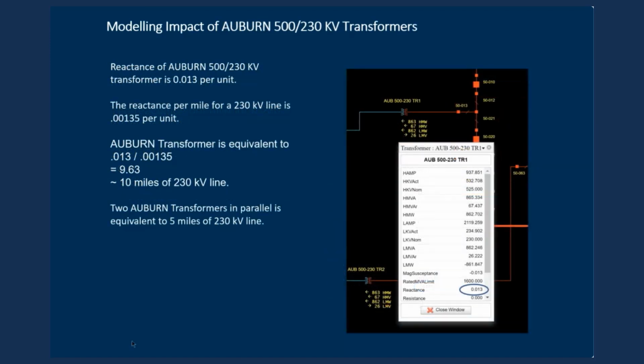The reactance of the Auburn 500 to 230 kV transformer is also 0.013 per unit. Again, the reactance per mile for a 230 kV line is 0.00135 per unit. So the Auburn transformer is equivalent to 9.63 miles, or approximately 10 miles of 230 kV line. Because we have two Auburn transformers in parallel, the parallel combination is equivalent to 5 miles of 230 kV line.